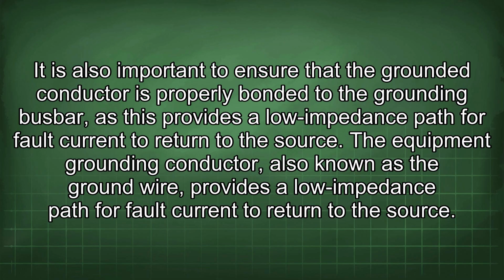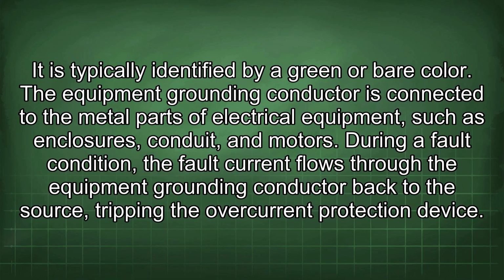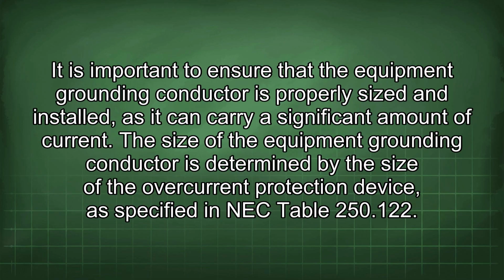The equipment grounding conductor, also known as the ground wire, provides a low impedance path for fault current to return to the source. It is typically identified by a green or bare color. The equipment grounding conductor is connected to the metal parts of electrical equipment, such as enclosures, conduit, and motors. During a fault condition, the fault current flows through the equipment grounding conductor back to the source, tripping the overcurrent protection device. It is important to ensure that the equipment grounding conductor is properly sized and installed, as it can carry a significant amount of current.